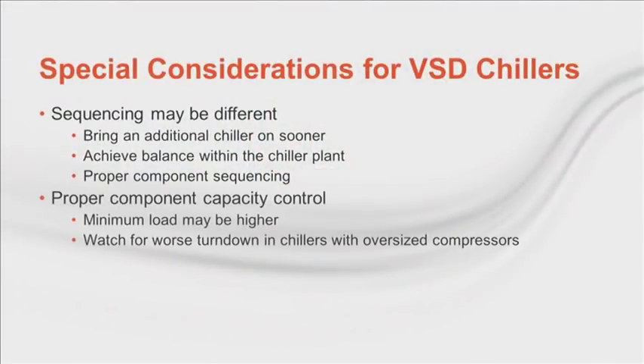Variable speed chillers unload differently. That should not surprise anybody. As with any variable speed device, the important attribute is turn down. How much can we slow down? It's tempting for chiller manufacturers to put a really large variable speed compressor on a chiller and never run it at full speed. This gives better full load performance, but may result in odd performance at other load points, sometimes even resulting in the need for hot gas bypass, which wastes energy.